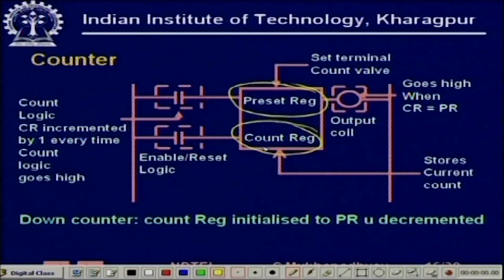For the counter, you are trying to count something — maybe the number of parts produced or the number of parts arriving on a conveyor. With every event taking place, you have to generate some kind of a pulse using contacts and sensors. Those external pulses will increment the count register. So in place of internal clock pulses used by the timer, here we have external pulses triggered by the events we want to count.